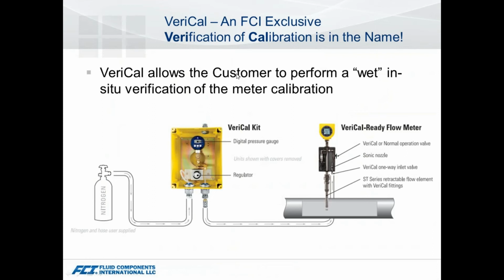The way VeriCal differs from the self-test is that in VeriCal mode, we're exercising the entire flow meter. This is more of a wet verification. Basically we have a sonic nozzle and the control valve, and on the inlet, you're going to want to regulate the pressure to a known value. Based on that, we're creating a very repeatable condition across the flow element. Again, it's not specific to a flow rate, but it gives me a measurable, repeatable value. I can compare the day I install it to 6 months or a year down the road to make sure my meter is giving me similar performance. It's really the ability to have a higher confidence in your meter performance and your readings.